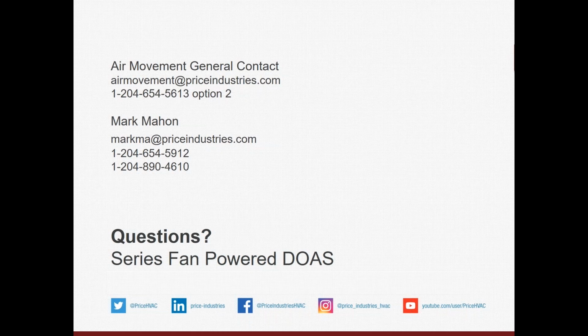Yeah, that's a great question. So we will factory mount any VAV controller or any temperature control valve for the hydronic side as well. We are aware that frequently the valve body supporting valves are very much part of the mechanical bid, whereas it's more of the control contractor's bid to provide the temperature control valve or DDC controls. So that's always something that we facilitate, and that's probably most frequent. What we see, we either see field mounted or we'll see factory mounted TCV and or DDC.